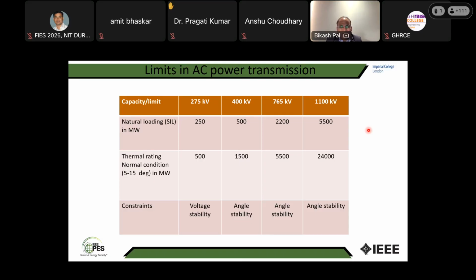The thermal one, essentially what happens? You have the conductors, these conductors are carrying current, so they will have an expansion. Because of the expansion, they will have a sag. And when there is a sag, there would be, of course, a change of the clearance. But particularly when these conductors are connected at the substation, in the first tower, there would be some kind of support from which this conductor will start.